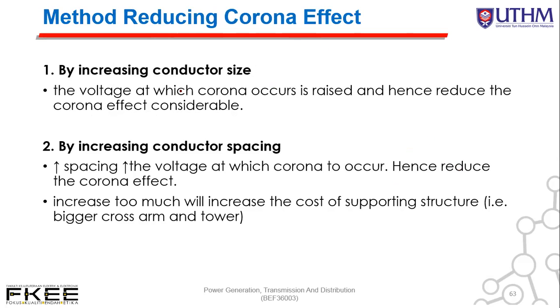Method to reduce corona effect: first, by increasing conductor size. Increasing conductor size, so the voltage at which corona occurs is raised and hence reduces the corona effect considerably. Second, by increasing conductor spacing. Increase the spacing, then the voltage at which corona occurs increases, hence reducing the corona effect. But increasing too much will increase the cost of supporting structure. We need bigger cross arm and also much higher tower.